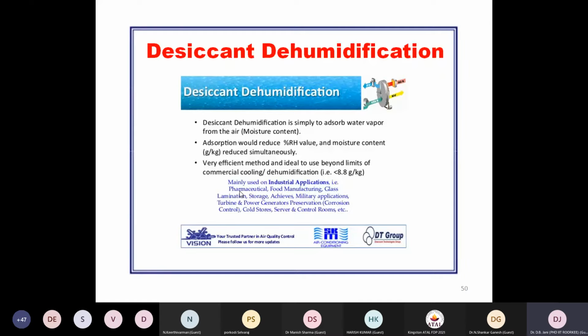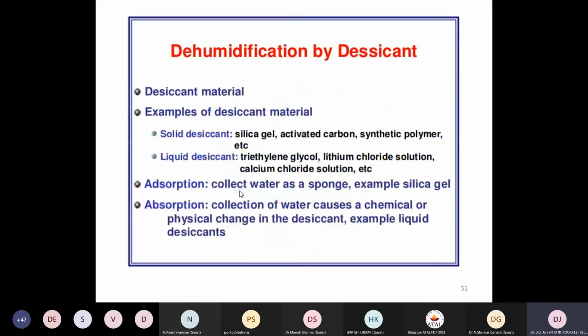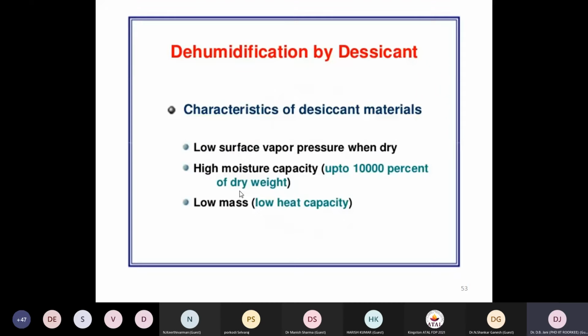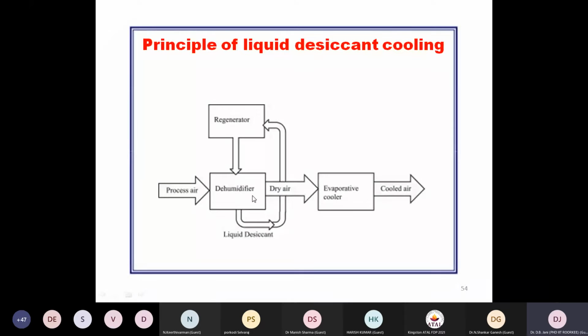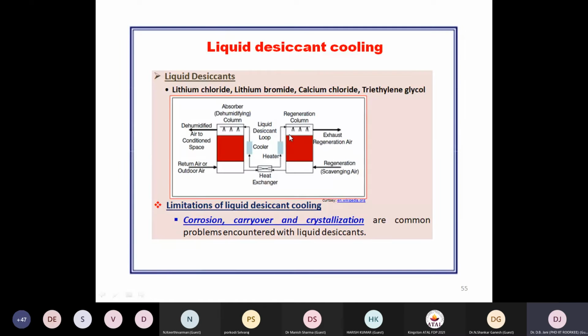So this is all about how the material is selected as a desiccant. It should have a high moisture absorption capacity. All materials are not desiccant materials. Some specific materials, which I have described earlier, can be selected as desiccants. It should have the capacity to absorb around 100 times its dry weight in moisture. So typically, in principle, process air first passes to the dehumidifier, is converted to dry air, gets further cooled, and is supplied to the room. And the regenerator provides hot air for the reactivation of the dehumidifier. So this is liquid desiccant cooling and its working.